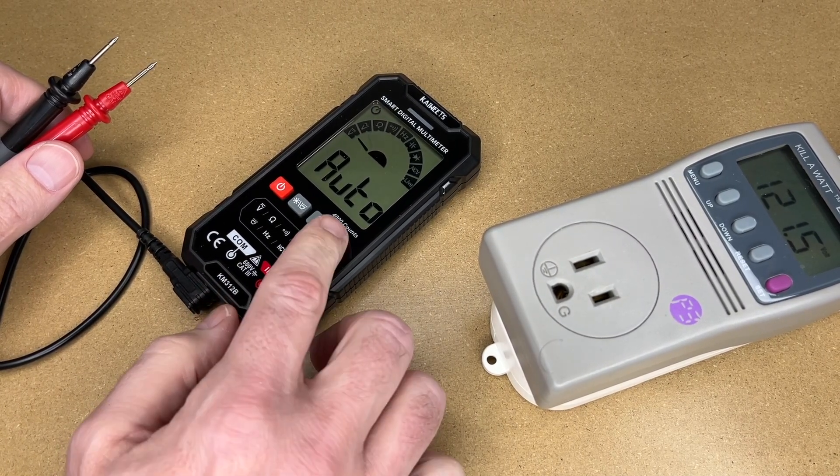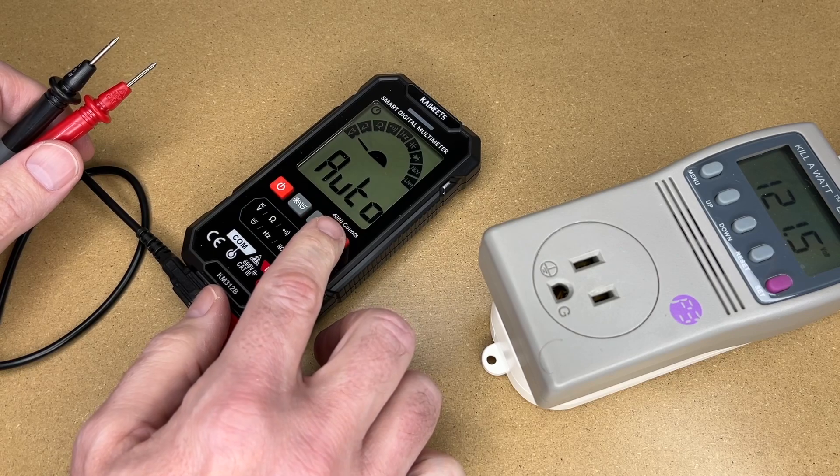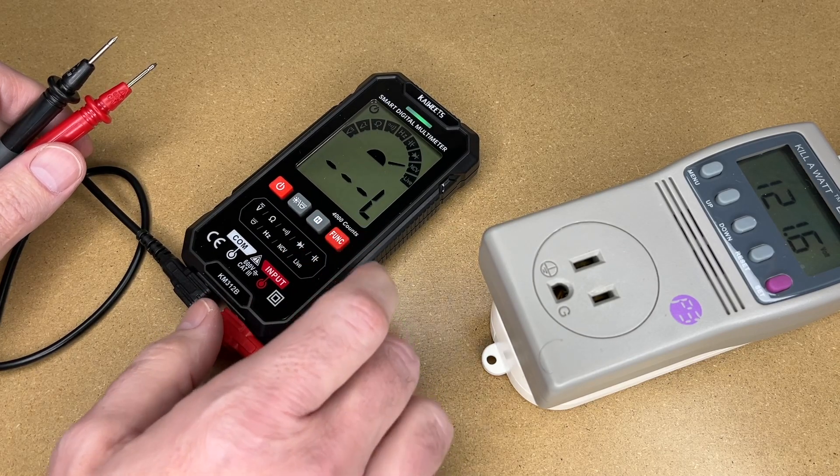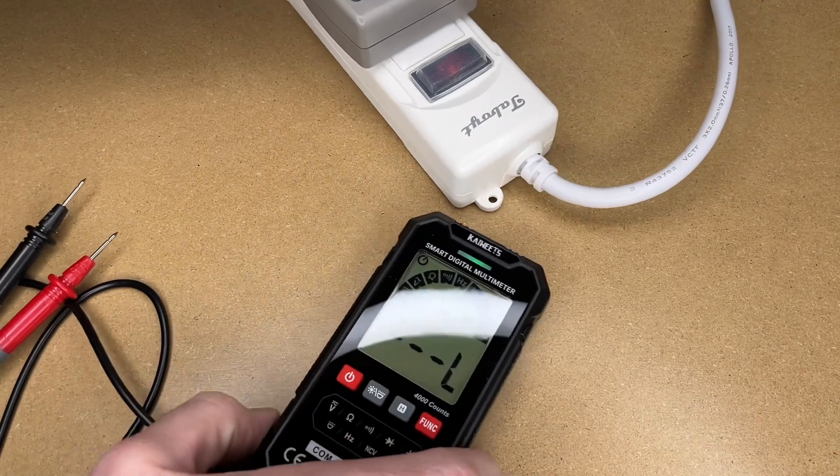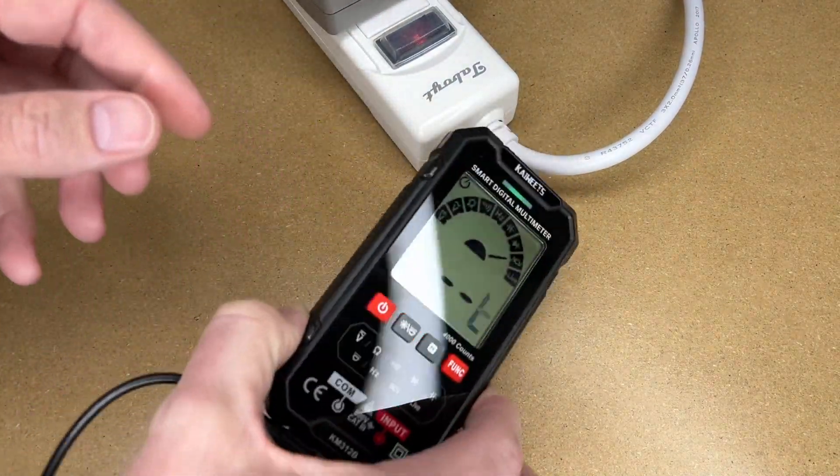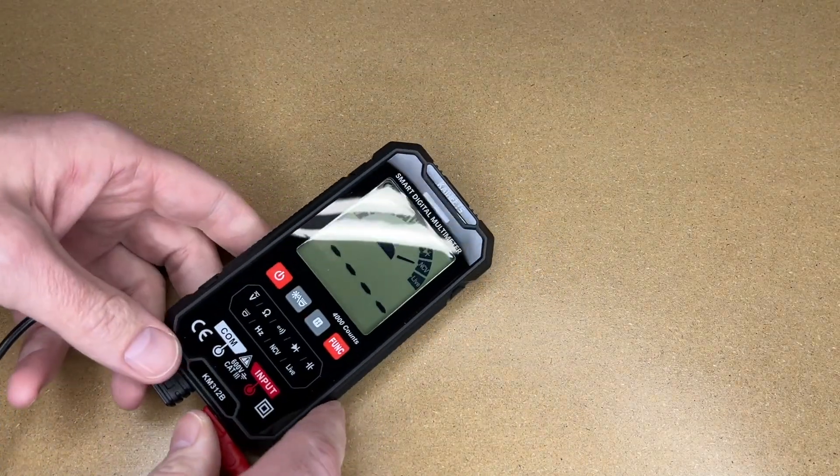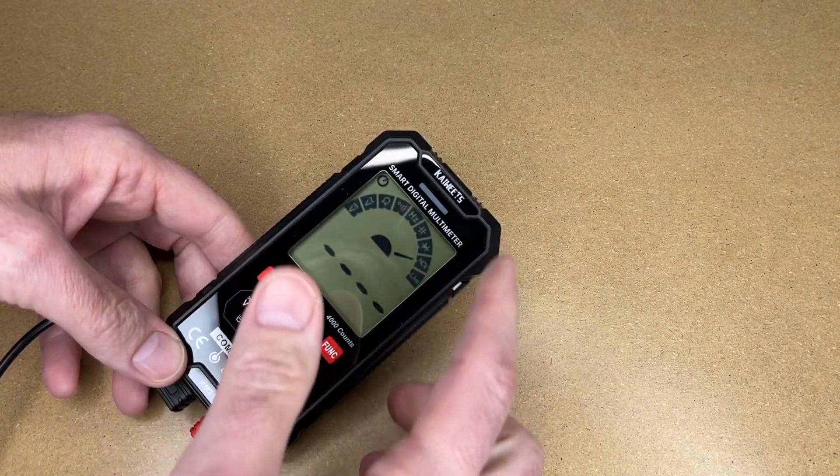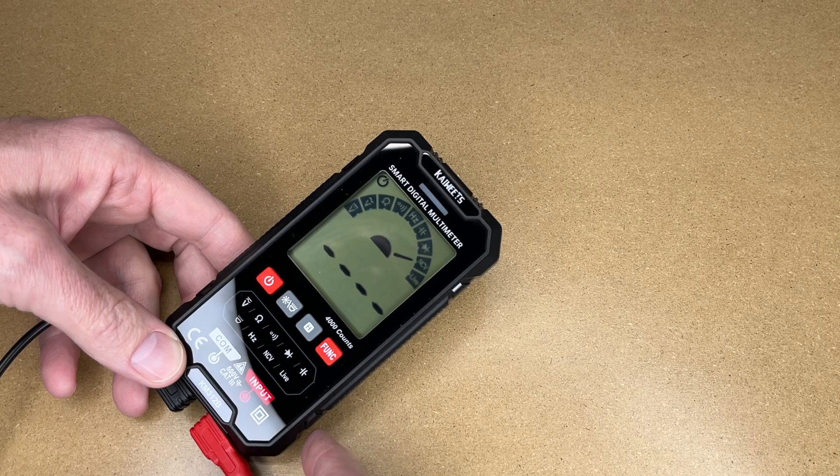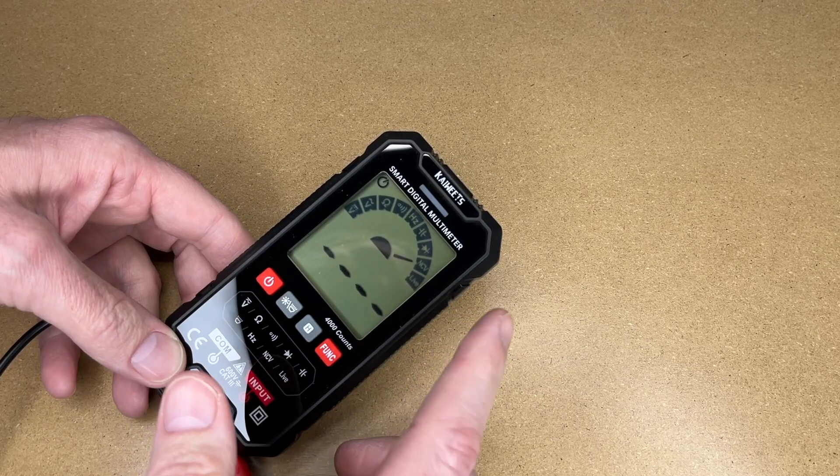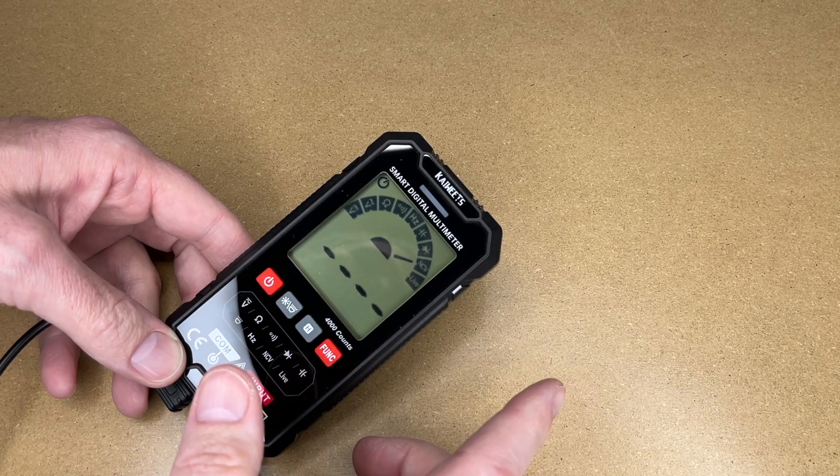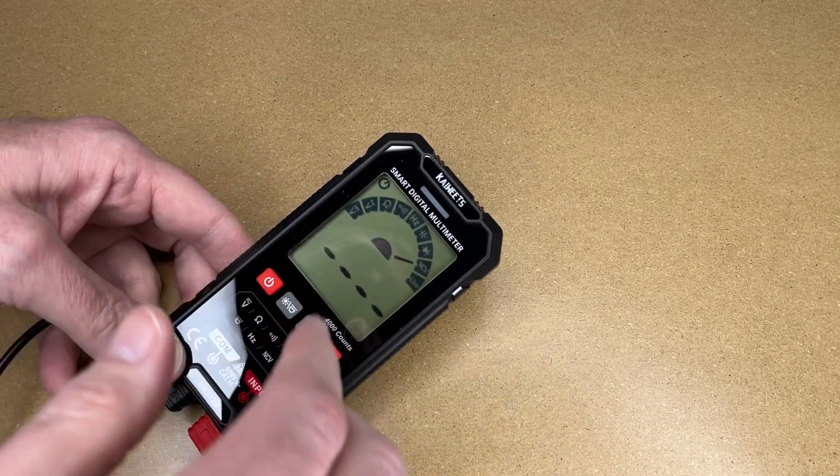Next, let's go to non-contact voltage. If I go up to this AC line here, there's a detector—I'll hold that up against the wire and it says it's hot. That's really handy: after you turn off a circuit you can test with that to make sure there's no electricity. With a non-contact voltage detector you typically want to test it with a known good power source to make sure it's actually triggered, then test the wire you're trying to test.